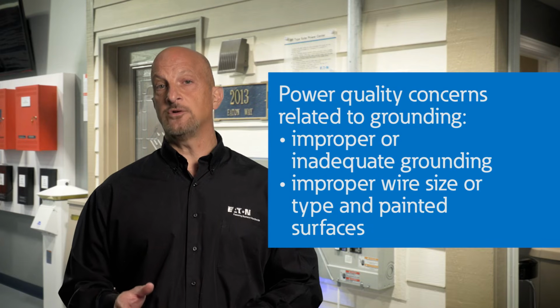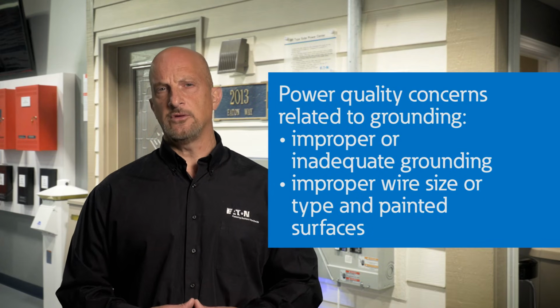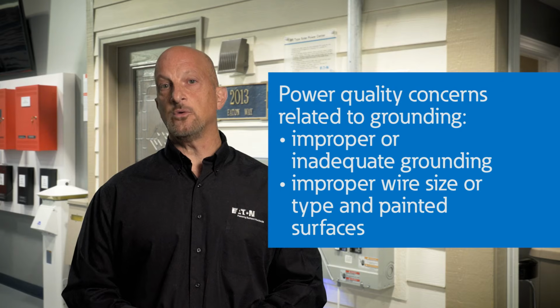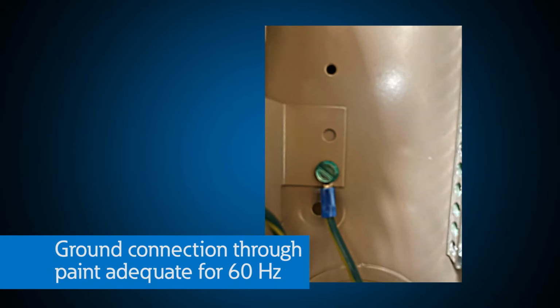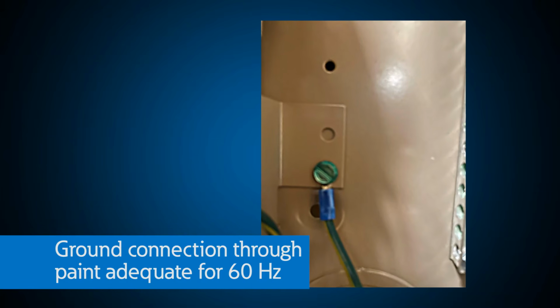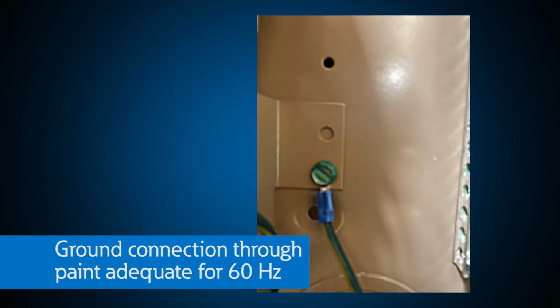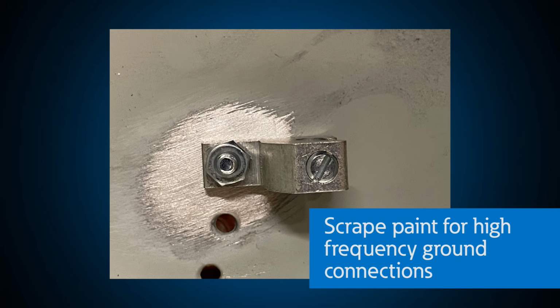Improper wire size or type and painted surfaces are also concerns. For example, 60 Hz currents will generally penetrate painted surfaces during fault conditions, but oftentimes higher frequency currents may or may not be adequate to provide a low impedance path for stray or unwanted currents from electronic components or induced currents from PWM inverters.